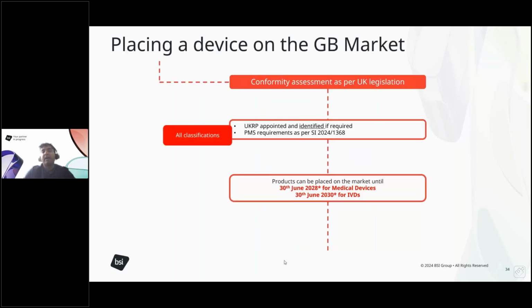And then we look at conformity assessment as per the current UK legislation. So we're talking about the UK MDR 2002. So for all classifications, UKRP are appointed and identified if required, and the PMS requirements have to be met. And products can be placed onto the market until, at the moment, 30th of June 2028 for medical devices and 30th of June 2030 for IVDs. However, these transition timelines may change dependent on when new legislation comes into force and new transition timelines come into force from the MHRA.